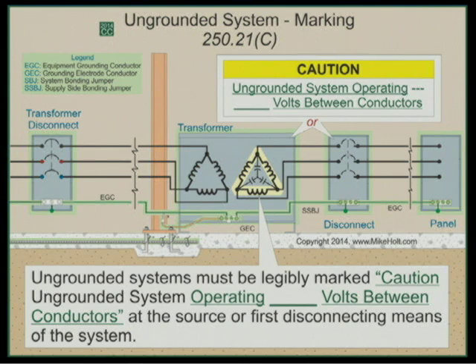Now, if you have an ungrounded system, the code requires us to put a label identifying what the voltage is between conductors. Without any kind of direct connection, even through light bulbs, there is no voltage between any of these phases and the enclosure. So you can't say there's any voltage to ground. The voltage is only between the conductors. That's a code change. All right.